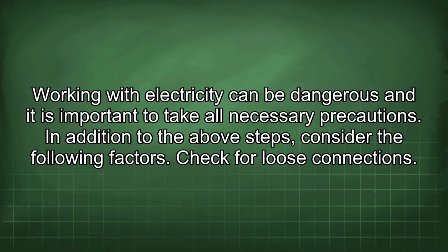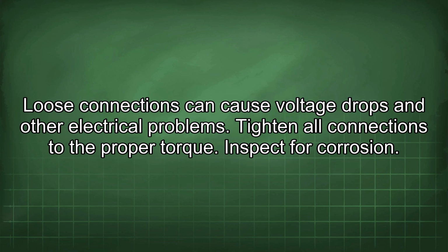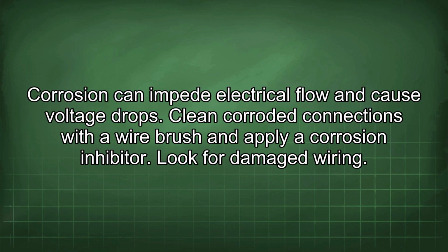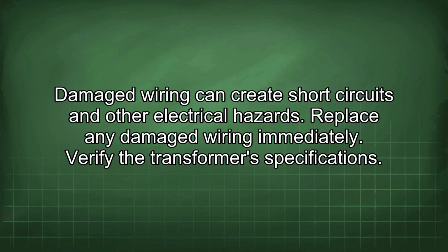Check for loose connections. Loose connections can cause voltage drops and other electrical problems. Tighten all connections to the proper torque. Inspect for corrosion. Corrosion can impede electrical flow and cause voltage drops. Clean corroded connections with a wire brush and apply a corrosion inhibitor. Look for damaged wiring. Damaged wiring can create short circuits and other electrical hazards. Replace any damaged wiring immediately.